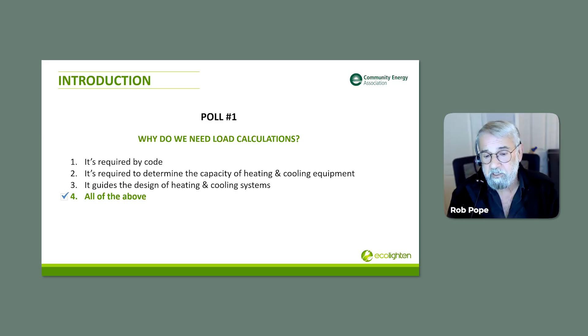It's a CSA, Canadian Standards Association standard, and that's the standard that governs the methodology of doing heat load calculations for residential buildings. It's embedded in the code, section 9.33.5. Using this standard, among other things, is going to ensure comfort.